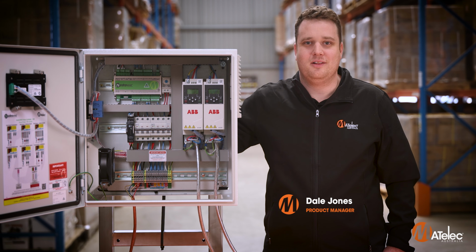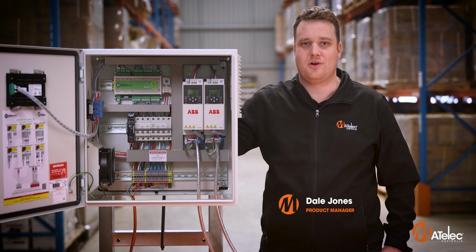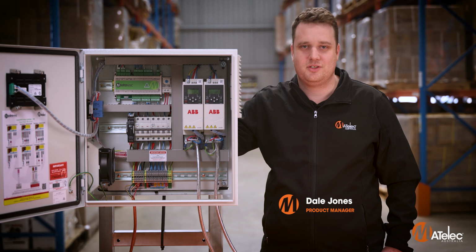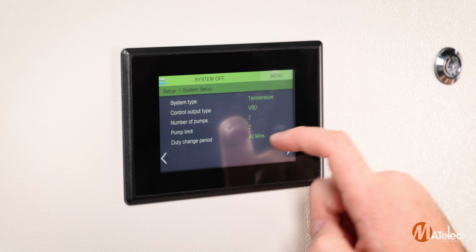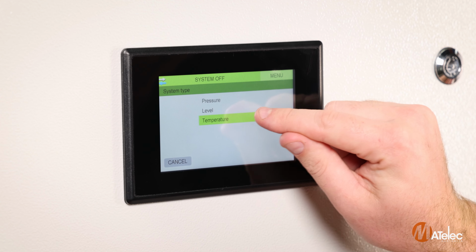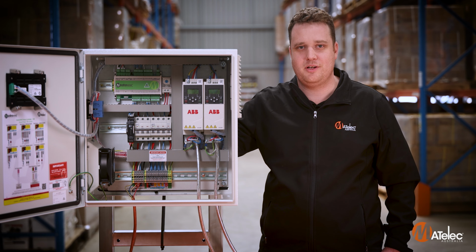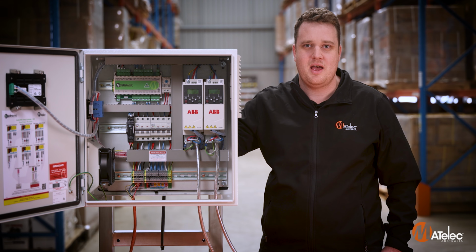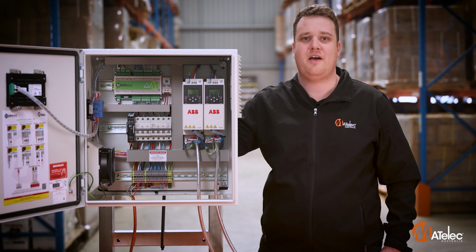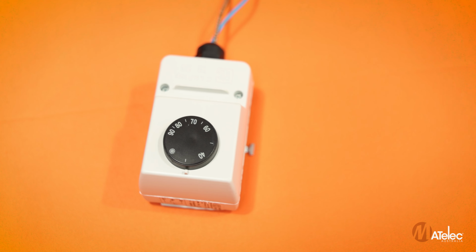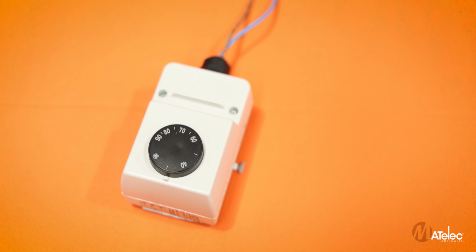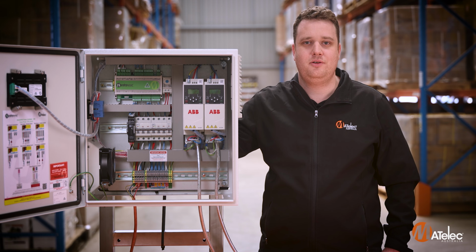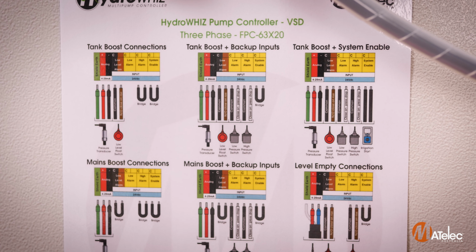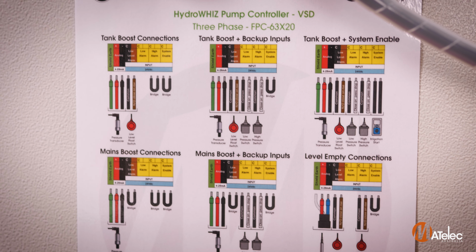Hello again. Let's look at temperature system control with the HydroWHIZ panel. So, you have a temperature configuration on your HydroWHIZ panel, which means your system runs with a temperature transducer, 4 to 20 milliamps, as the main input, and you have high and low temperature thermostats as backup if needed. Your panel comes with its own unique inner door label, showing exactly how the inputs are connected.